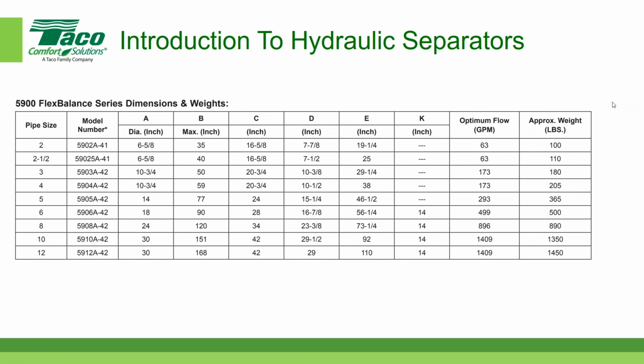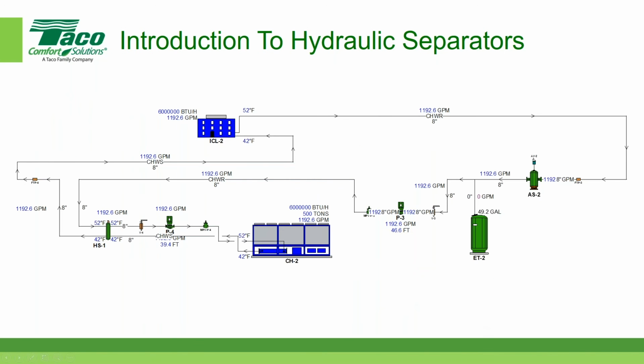So in our case, if you recall, we said our system had 1,200 gallons per minute. Actually, before I do this, let me go back to the diagram to refresh your memory. Let's go back to the piping diagram. If you recall, on the piping diagram, in order to accommodate this flow of roughly 1,200 gallons per minute, we have a pipe size of 8 inches. So for 1,200 gallons per minute and an 8-inch pipe, that's about 7.7 feet per second. So intuitively, you might say, okay, I've got an 8-inch pipe, I'm running 1,200 gallons per minute, and that's going to be approximately 7.7 feet per second. So I'm going to select a hydraulic separator that's an 8-inch connection.